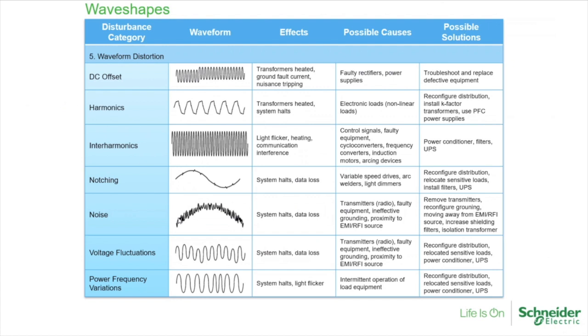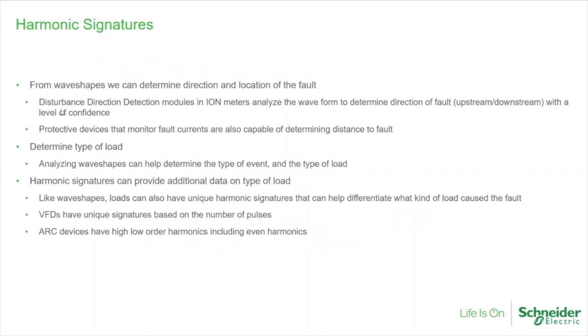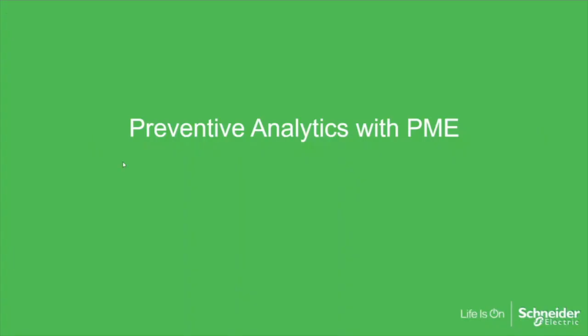So I'll probably finish up on the wave shapes because I wanted to get into the meter a little bit, and as he's going through the meter, talk about all the information that's available in meters today, and how to take advantage of that information and use it. These are some different waveform disturbances: DC offset, harmonics, interharmonics, noise, voltage fluctuations. Then there are a couple of things on signatures. Wave shapes can have unique signatures, and over time you can build a database and be able to recognize transients and sag swells, and further differentiate what kind of load could be causing it. Same with harmonics: a lot of devices like inverters, VFDs, and arc devices typically generate the same harmonics, so that can help you identify what's causing them.